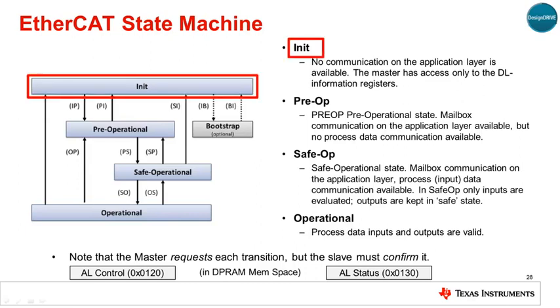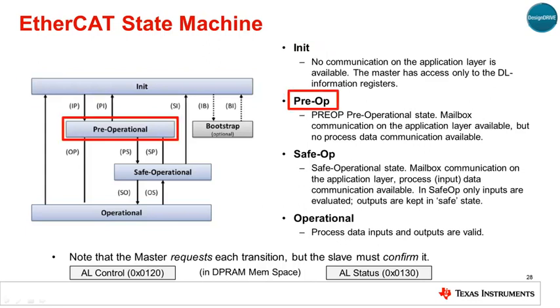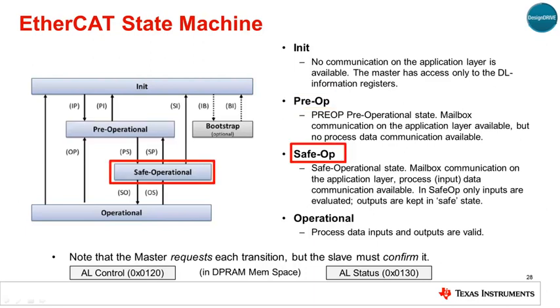In the init state, no communications on the application layer is possible, and only the master has access to the data link information registers. In the pre-op state, mailbox communication becomes possible, but there is still no process data exchanged to the master — this can be thought of as a machine setup state. In the safe-op state, communication to the application layer is available, but only inputs are evaluated; outputs are kept in a safe state. This correlates with the desire to know the state of a factory machine prior to exercising the outputs.